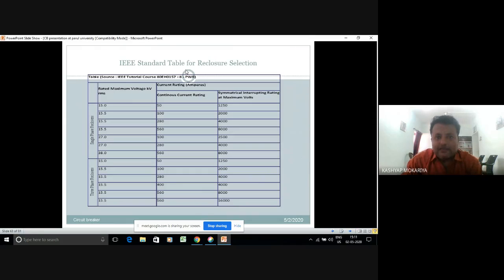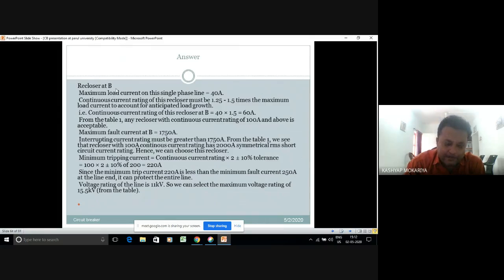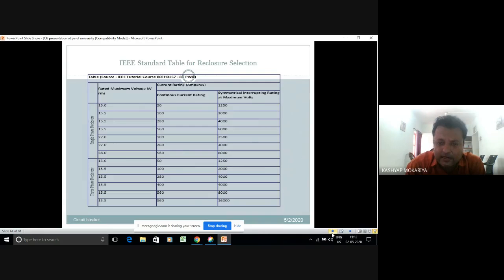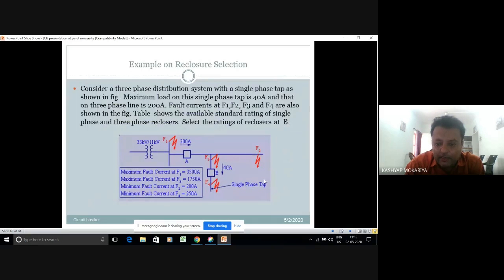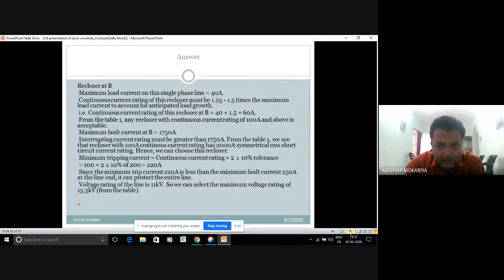So this is the IEEE standard table for recloser selection. At the left side you can see the recloser voltage, the voltage rating. At the right side you can see a continuous current rating and a symmetrical interrupting rating at maximum voltage. So let's go for a design part of recloser also. So recloser at B. What was the maximum load current at the line? You can see here it was 40 ampere. The 40 ampere was the maximum load current there.